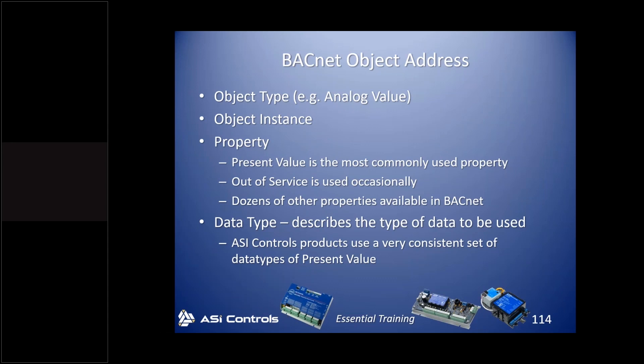Zero-based counting is a little odd at first but becomes intuitive after you do it a few times. There's also what's referred to as a property in BACnet — almost always from a front-end standpoint, Present Value is the property we want to access. There are other properties like Out of Service, which can be used to override an output or input. To override an input, you have to set the Out of Service flag before writing to the Present Value, because an input is normally read-only.